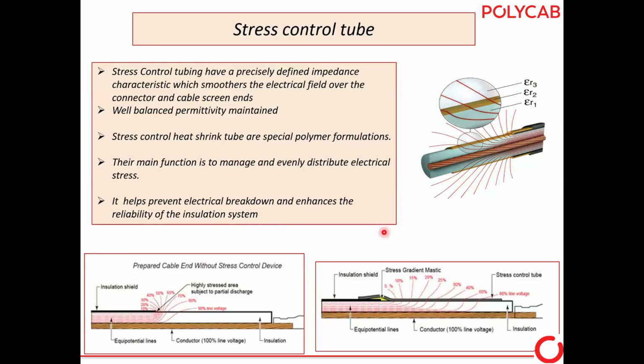So for the stress control tube, I have shown here two examples. One is without a stress control tube and another with a stress control tube. In the first photograph you see the conductor. We have prepared the conductor. Over that is the XLP insulation, and over that we remove the semiconducting layer up to that point. And if we do the connection of the cables and charge the cable at this position, you can see the flow of equipotential lines.